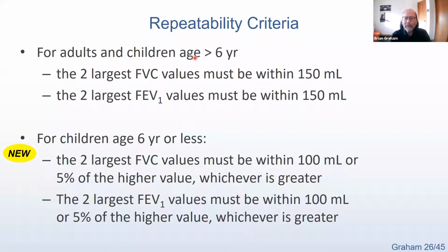So the repeatability criteria are staying pretty much the same. The 2 largest FVCs within 150 mils, the 2 largest FEV1s within 150 mils for anyone over 6 years of age. There's a bit of a change here for children 6 or less, and that is that they must be within 100 mils or 5% of the higher value, whichever is greater. And similarly for the FEV1. So there's been a bit of a change there.